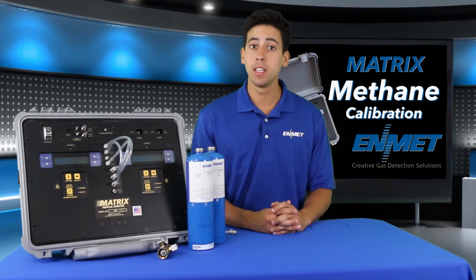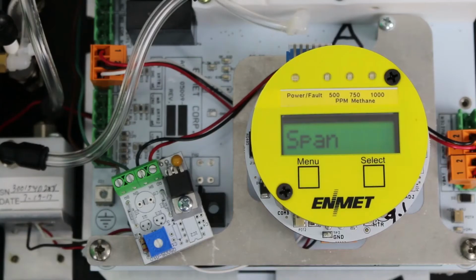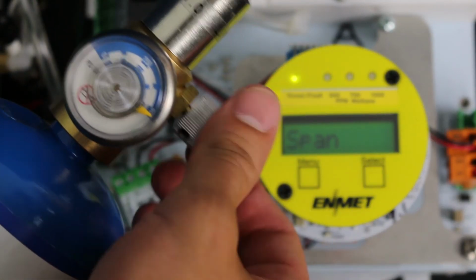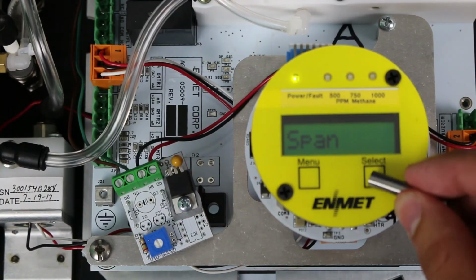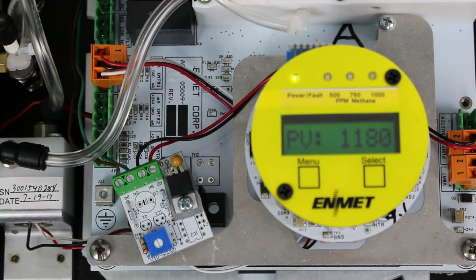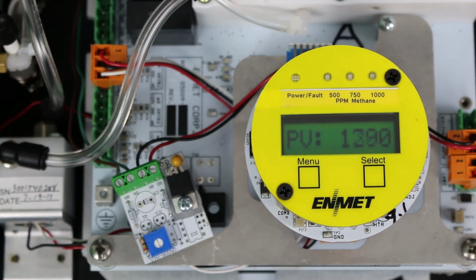Now, for the spanning, connect your span gas, 0.1% by volume methane, and open the valve on the regulator. Press the select button to begin the span procedure. The display will alternate between Cal 1000 and PV. Again, PV stands for present value.